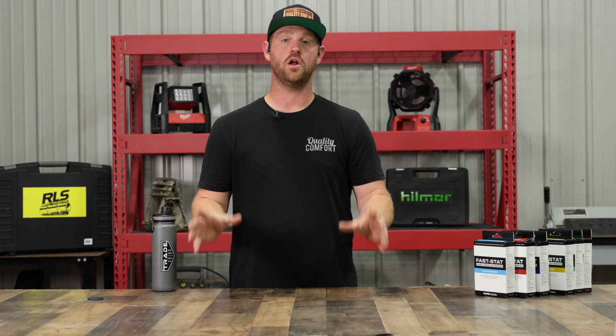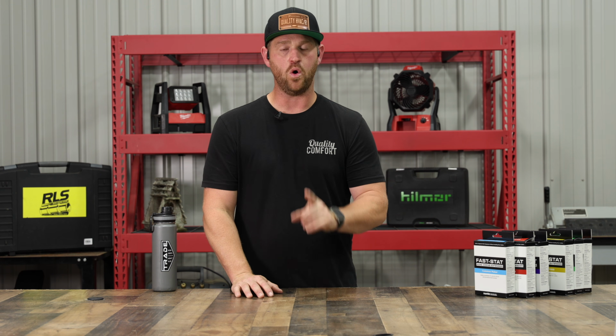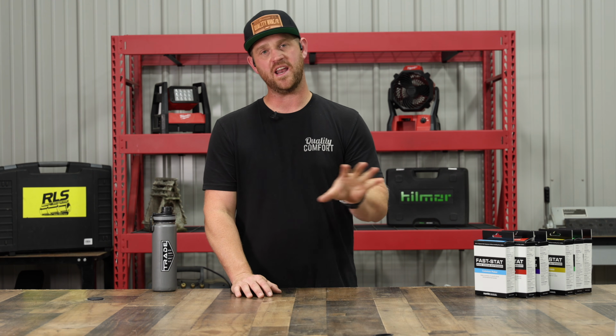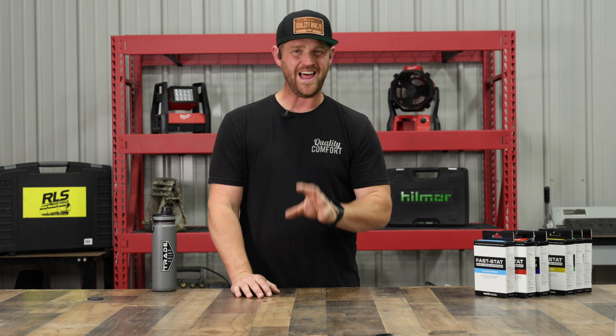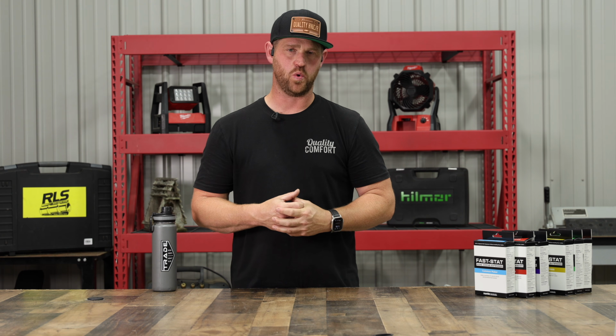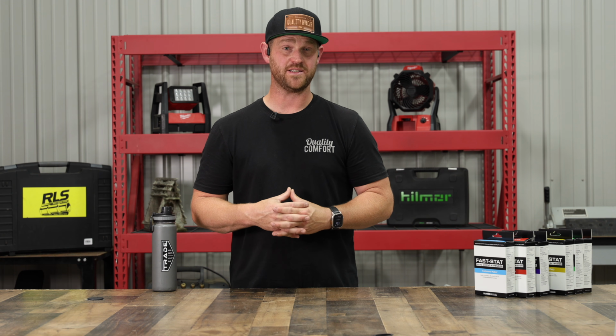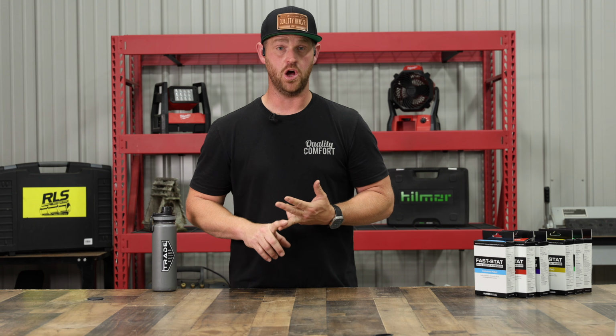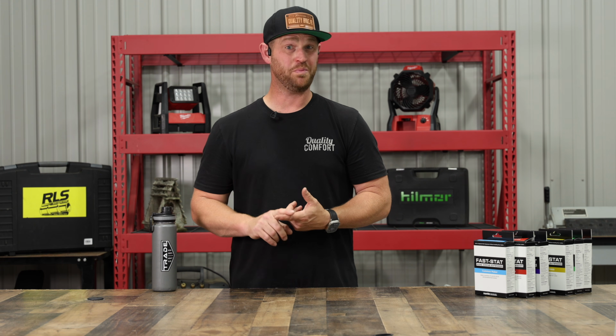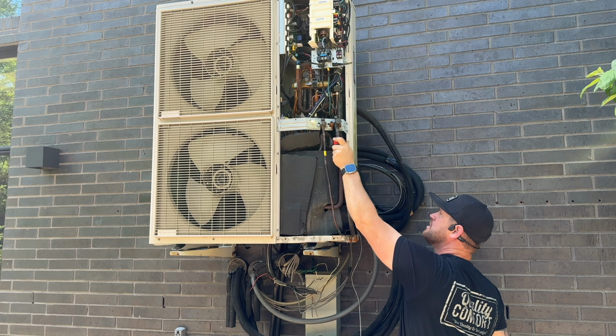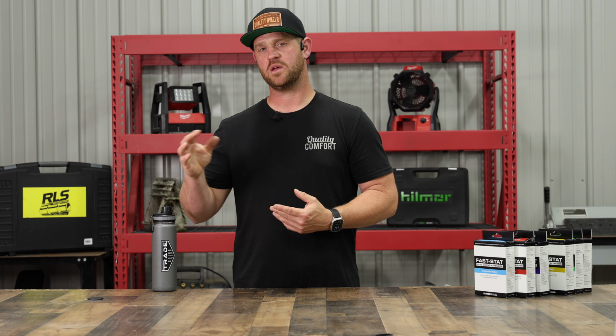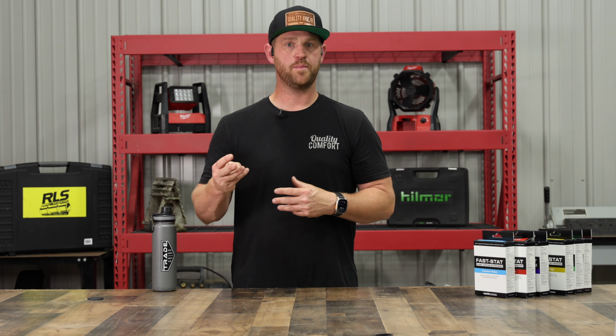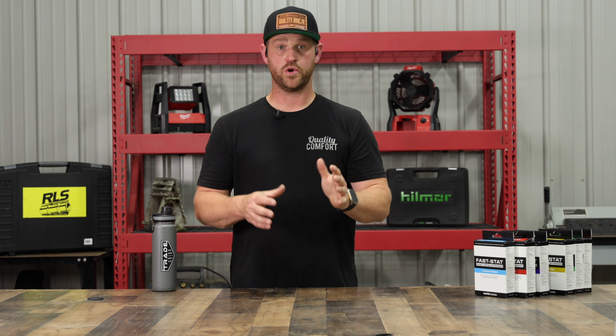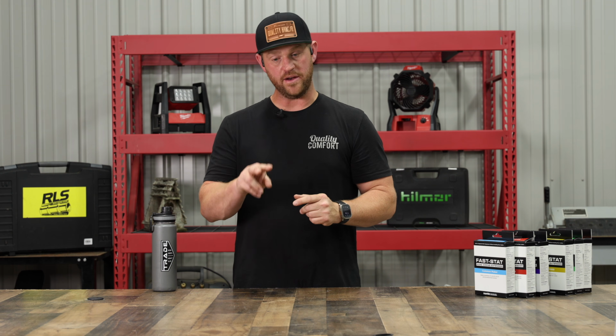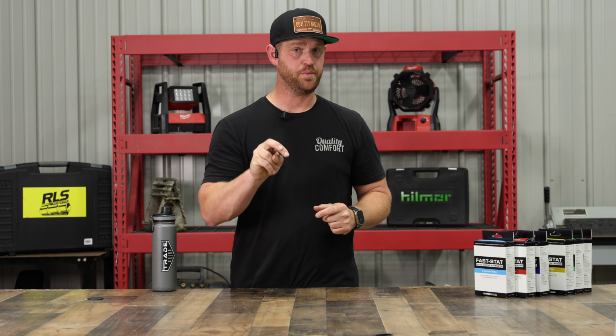I mean, we could go on and on and on about the different types. I wanted to talk about the VRF. I think I kind of got veered off a little bit. The last kind of part of this whole equation is VRF systems. Now that stands for variable refrigerant flow. There are 2-pipe systems. There are heat recovery that are 3-pipe systems, but that's typically more in a commercial application. The 3-pipe is where you have, let me back up. And a VRF system is where you have one condenser, one outside unit, and one line set coming off of it. So 2 pipes.